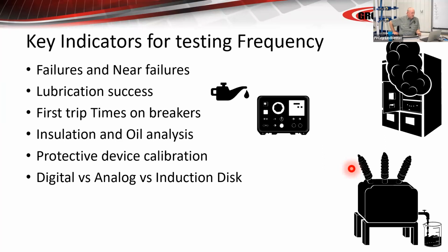Now we're just talking about circuit breakers, not talking about relaying as much, but the two systems work and have to be maintained in concert. But when you're dealing with circuit breakers, if you can gather first trip data, and you look at it and it's consistent, and then it starts to fall off, that's the point you need to address maintenance interval and lubrication or both. You know, oil analysis, insulation analysis is a big part of your overall maintenance plan.